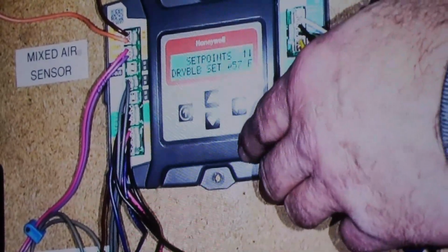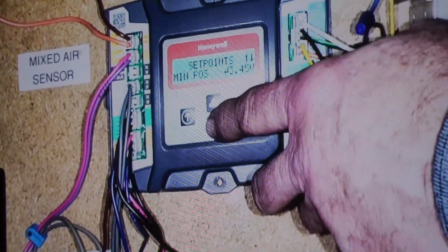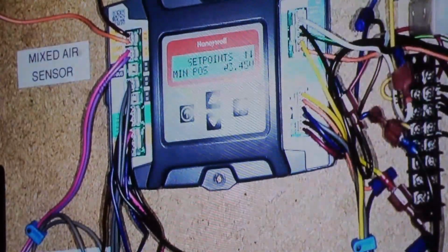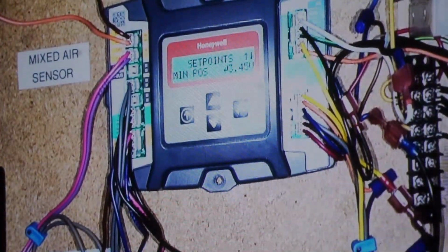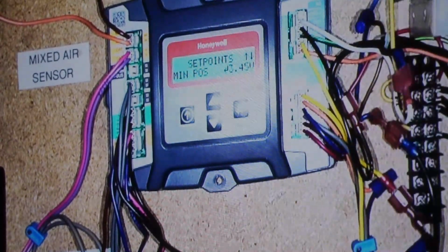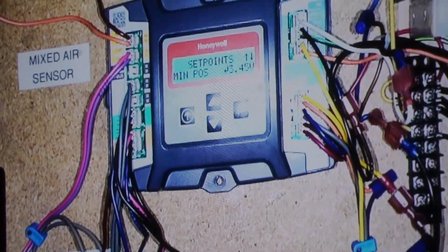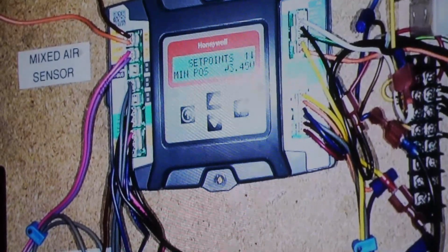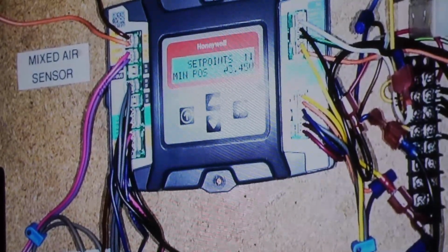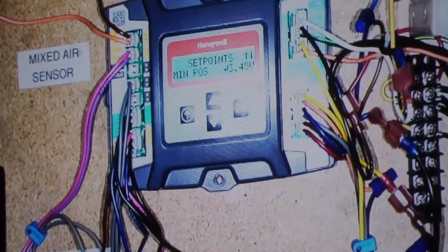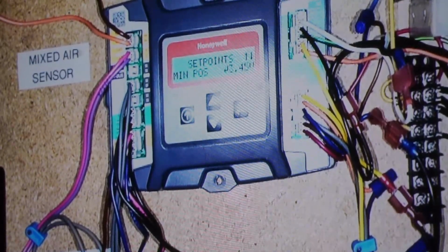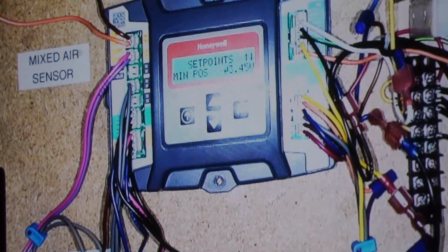Dry bulb set point is 57 degrees. That's if we're using a dry bulb economizer. Minimum position, 3.45 volts. Takeaway to remember here is this is a 2 to 10 volt actuator, so from 0 to 2 it does nothing. We've got a span of 2 to 10, so roughly 8 volts. If we want 20% movement, that's 1.6 volts, right? So we're going to take that 1.6, add it to 2, 3.6 volts is going to give us about 20% outside air, or 20% of movement.